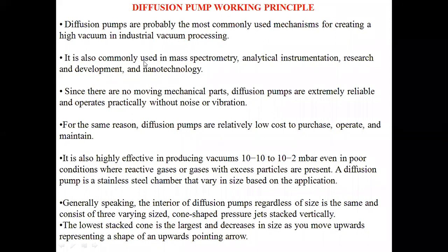Okay, fine then. It is also commonly used in mass spectrometry, analytical instrumentation, research and development, and nanotechnology. So these are the different applications of diffusion pumps. Since there are no moving mechanical parts, diffusion pumps are extremely reliable and operate practically without any noise or vibrations. First thing, my friends, these pumps make almost no sound, without any noise and vibration.